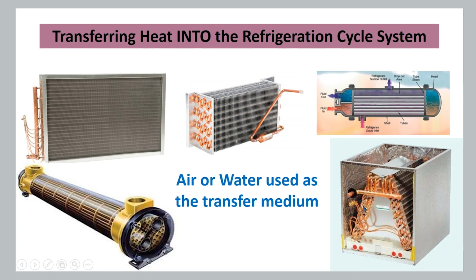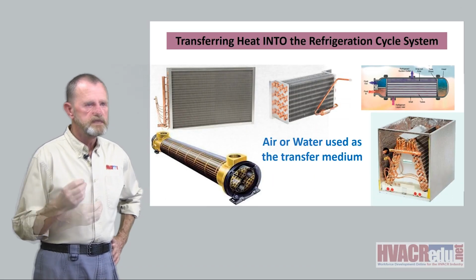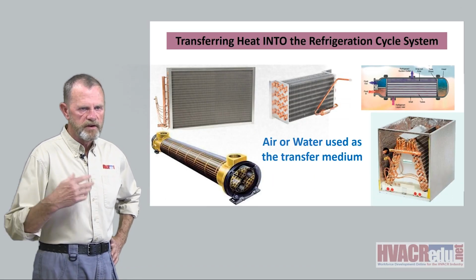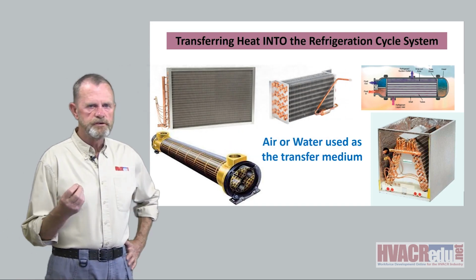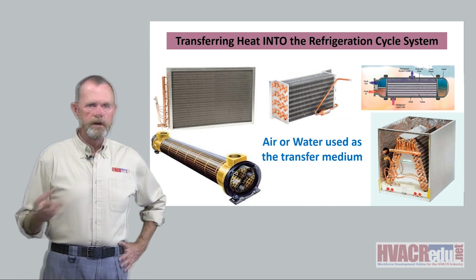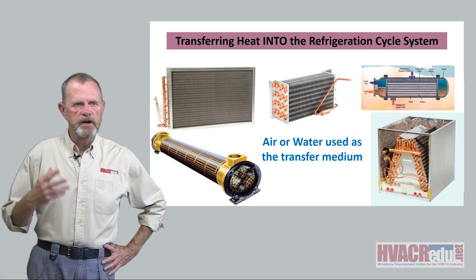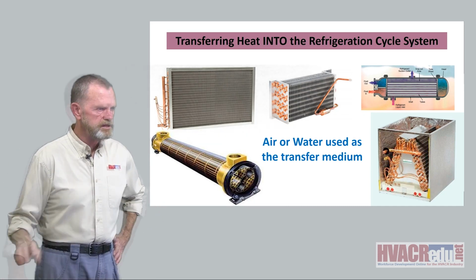And then I've got a chiller barrel here and a chiller barrel there, showing it's essentially the same thing in the water cooling business. You have to get a refrigerant system in the chiller barrel where you have evaporator tubing. You've got to get that refrigerant colder than the water coming in to get that heat to transfer out of the water into the refrigerant that's in the evaporator side of the system.